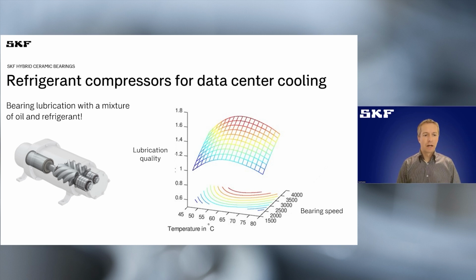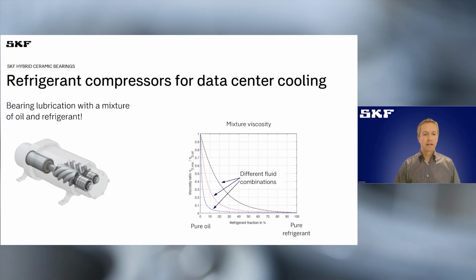Let's have a look at how the lubrication quality, or also the viscosity, is affected by this mixture of oil and refrigerant. In this diagram, you can see on the left-hand side the viscosity of the pure oil, which is maybe in the range of 100 centistokes. And on the very right-hand side, you can see the viscosity of a pure refrigerant, which is close to 1, similar to the viscosity of water.